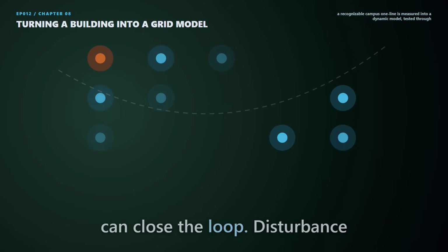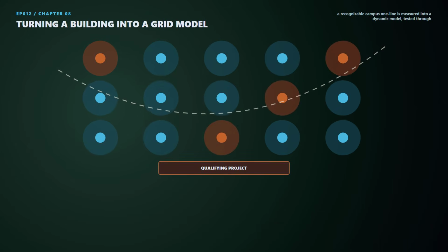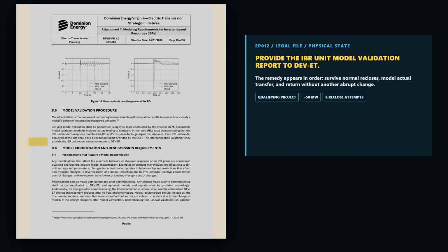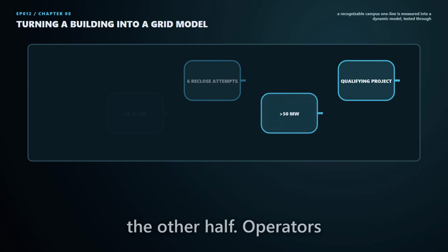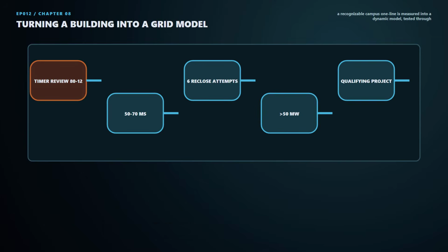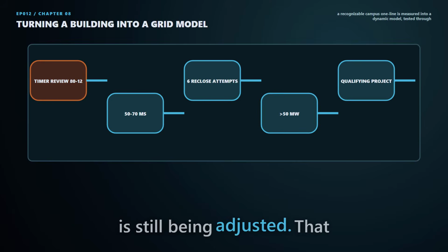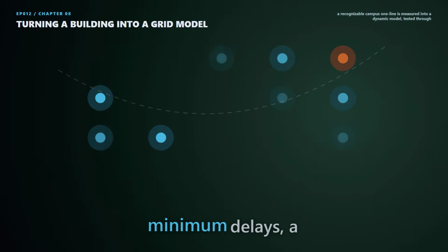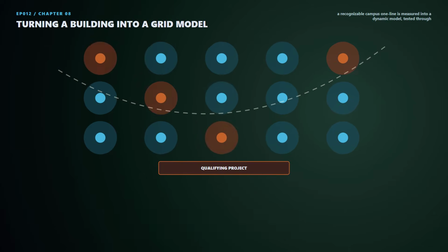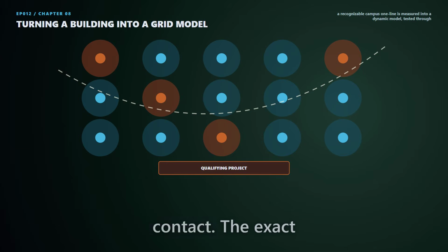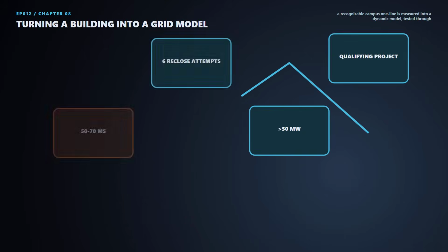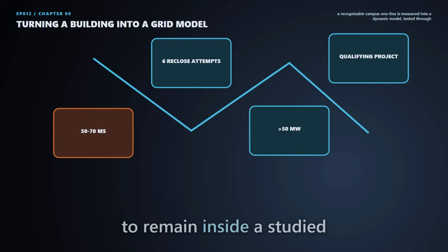Monitoring can close the loop. Disturbance recorders show the transmission voltage waveform. Customer telemetry could, where agreed and protected, provide transfer timing for model validation without exposing the computing work. Controlled reconnection is the other half. Operators need a way to avoid a sudden return while generation is still being adjusted. That can mean staged blocks, minimum delays, a communicated ramp, or coordination through an operating contact. The exact method can differ by facility, but the regional result has to remain inside a studied envelope.